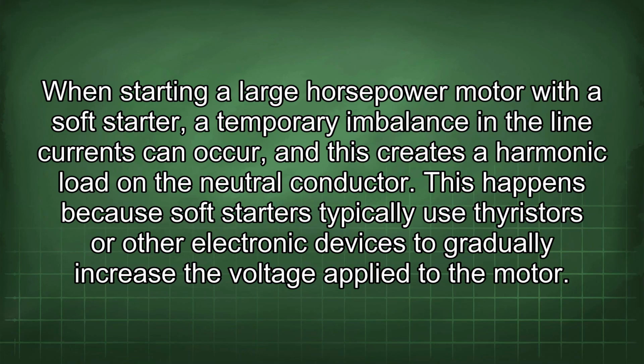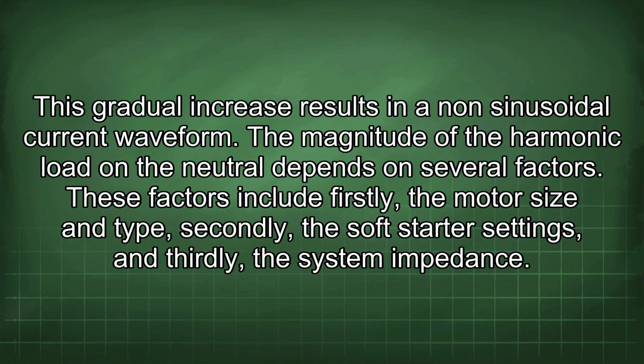When starting a large horsepower motor with a soft starter, a temporary imbalance in the line currents can occur, and this creates a harmonic load on the neutral conductor. This happens because soft starters typically use thyristors or other electronic devices to gradually increase the voltage applied to the motor. This gradual increase results in a non-sinusoidal current waveform.